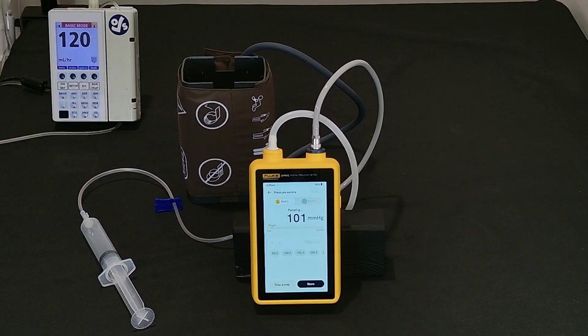And here you see our pressure pump pumping up to the desired pressure and holding that value. But a really cool feature about the pressure source is that if you were taking more than one measurement, you don't have to restart the test over.